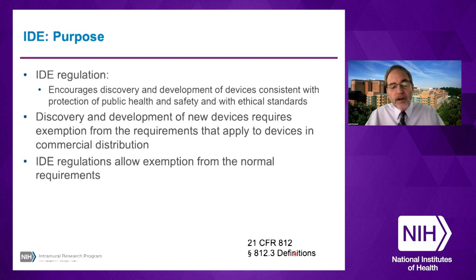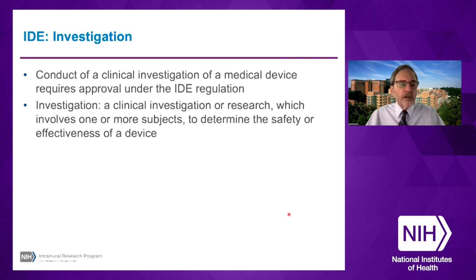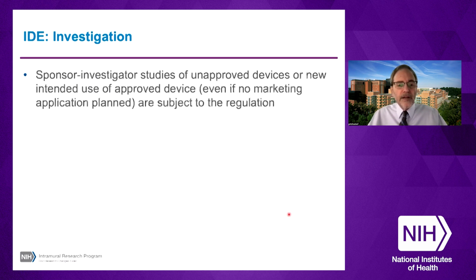And from here on out, I have a number of links to different resources, but 21 CFR 812 is what covers the IDE regulations. So the conduct of a clinical investigation of a medical device requires approval under the IDE regulation. Now, that doesn't mean you have to have an approved IDE from the FDA. It may be approvable by the IRB, but it has to be approved in accordance with the regulations. And an investigation is defined as a clinical investigation or research which involves one or more subjects to determine the safety or effectiveness of a device.